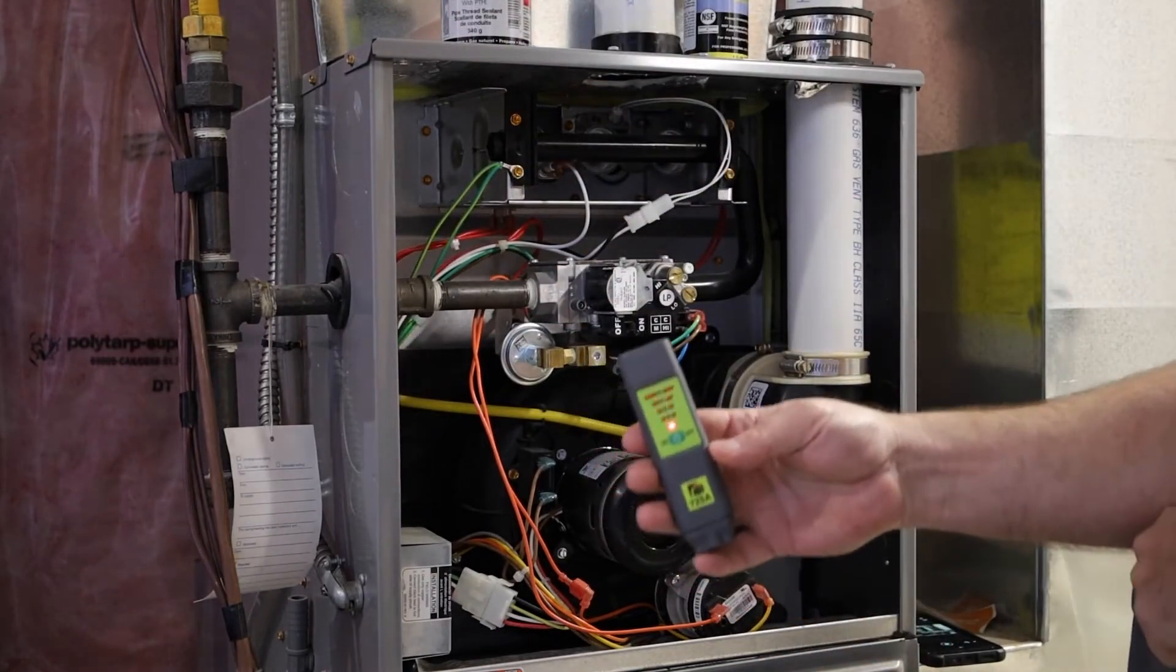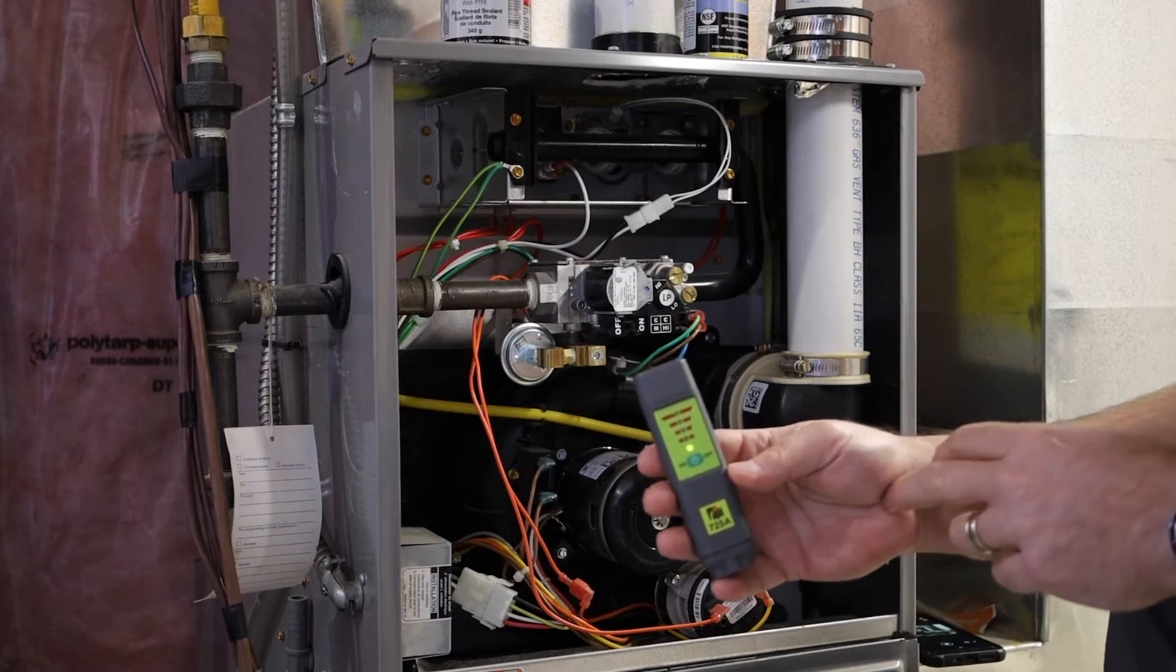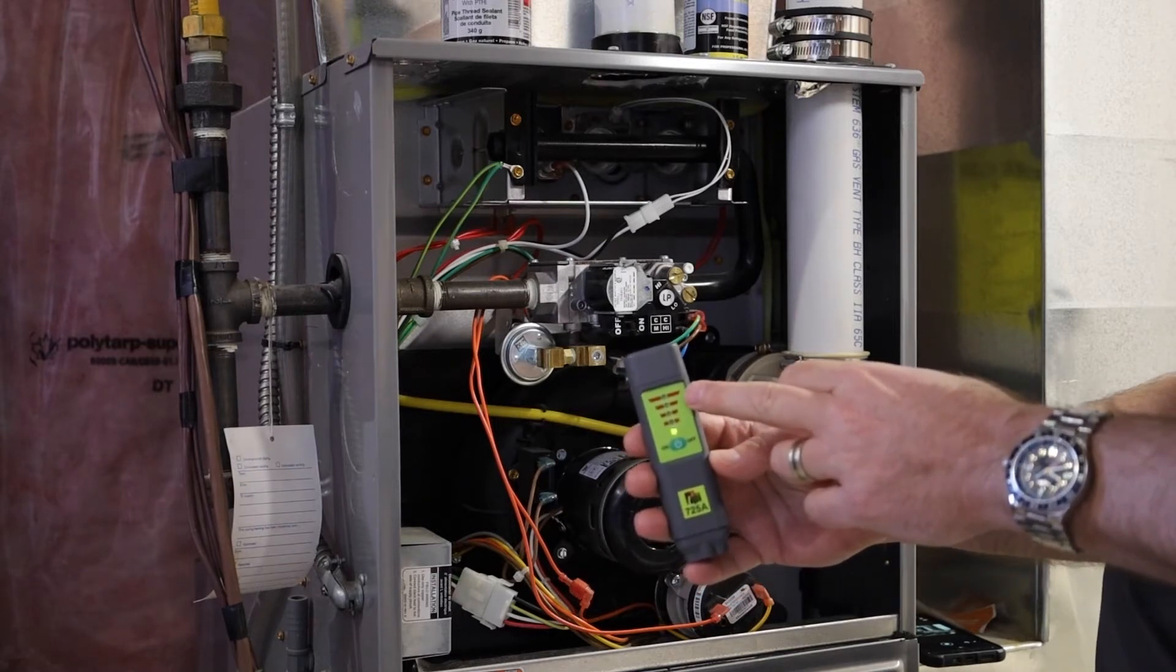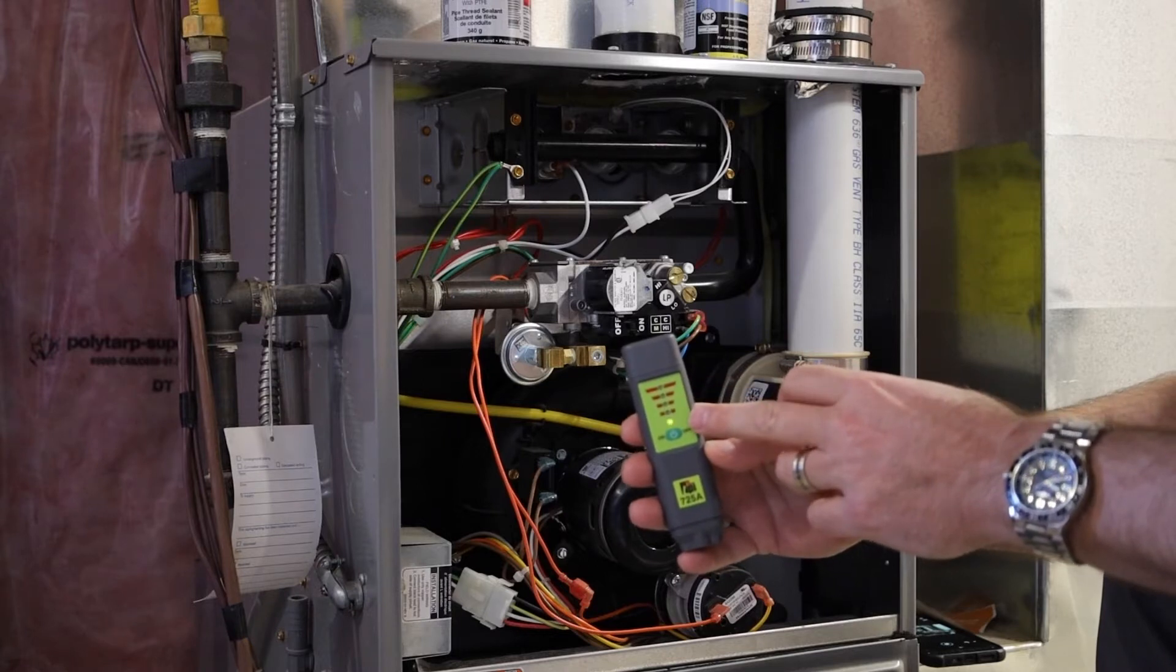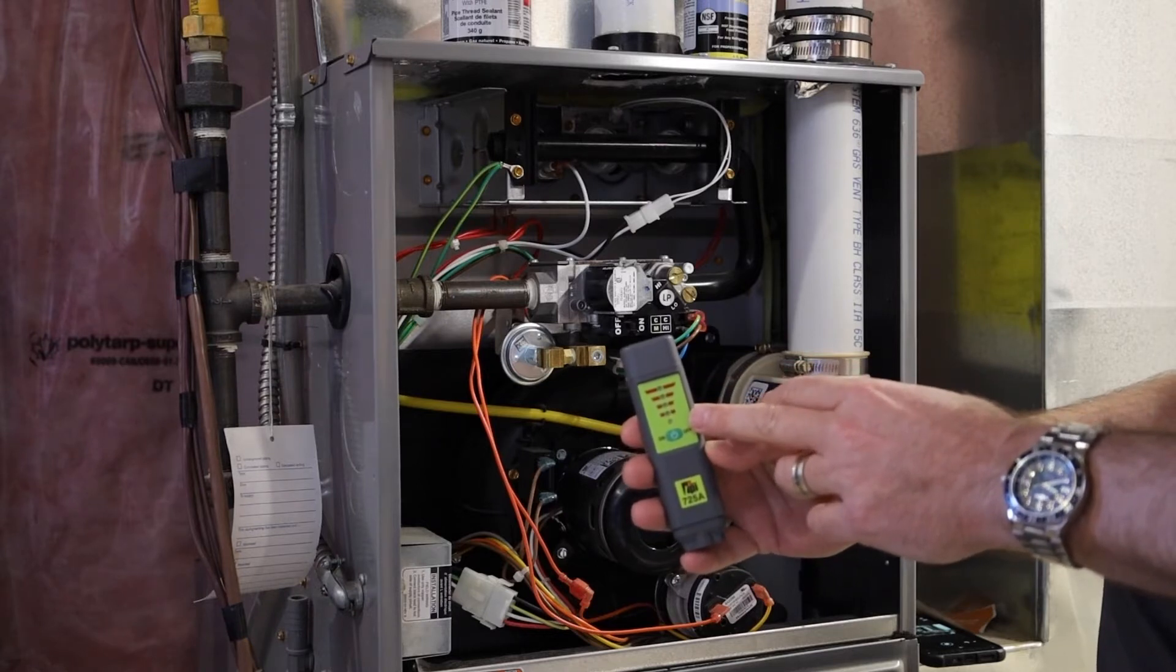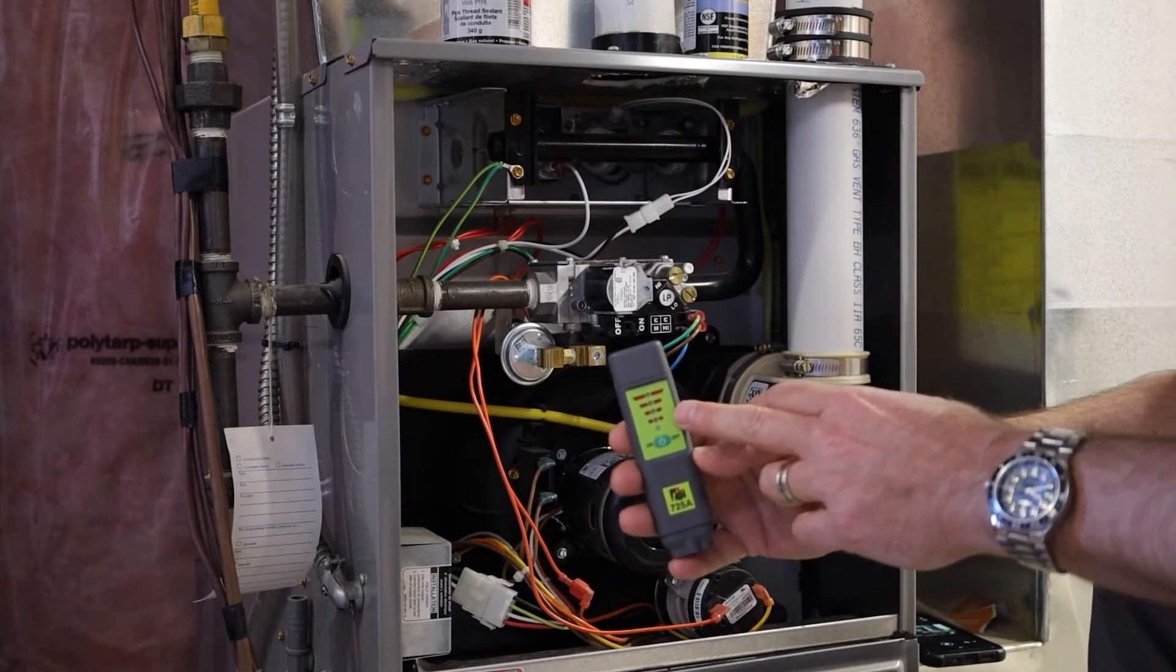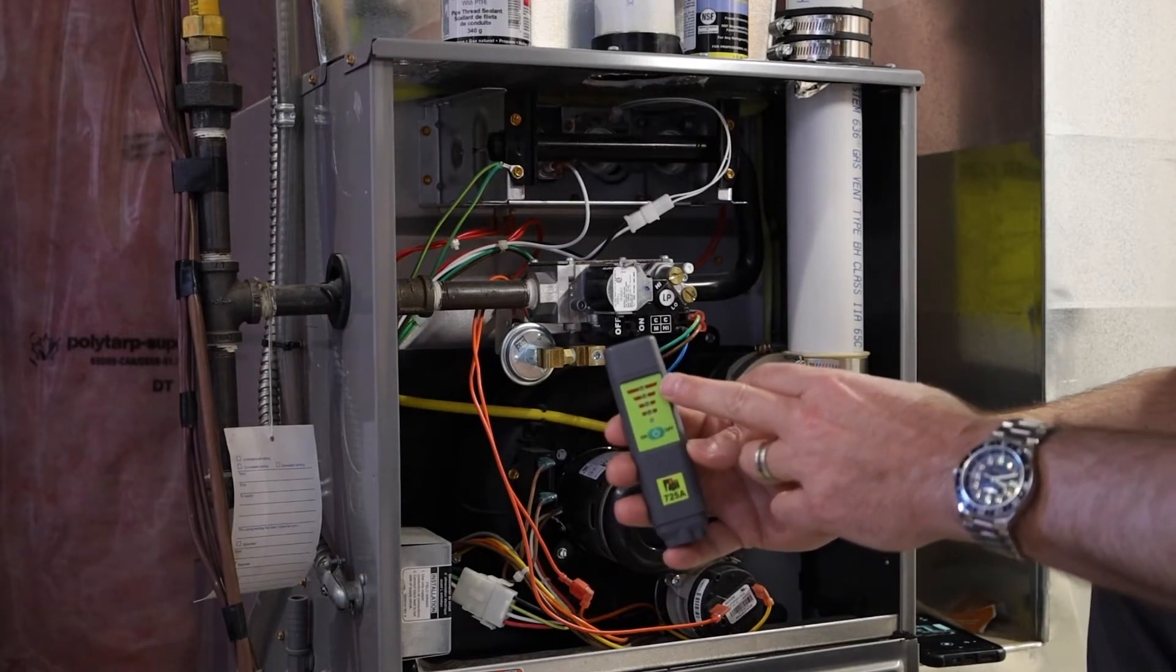There are indicating LED lights on here that indicate the size of the leak in parts per million. The first level would be under 500 ppm, then level two would be 1,000, 3,000, and then 5,000 ppm.